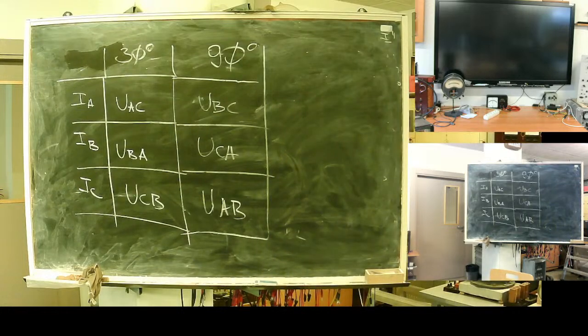Old time analysis showed that in 30 degrees there is a bit higher possibility of failed tripping of the directional relay in case the fault is on the client side after a delta-star transformer. But there is not very much difference.